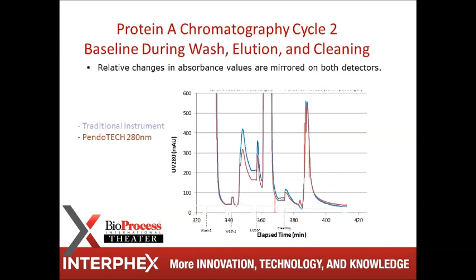Taking the sensors out of the loop for a second, a lot of metrology people have experienced a paradigm shift because they're used to very traditional instrumentation. So what's important is how do you qualify a monitor on its own, because a sensor has its own attributes which will be changed. So how do you qualify a monitor? Well, there's different tools that are available to check the different technologies without actually needing to use a sensor. So you're basically just verifying monitor performance. For pressure, you can apply a millivolt. Temperature, you can do a resistance simulation, same as conductivity. And absorbance, you can use absorbance standards to make sure the monitor is performing correctly.